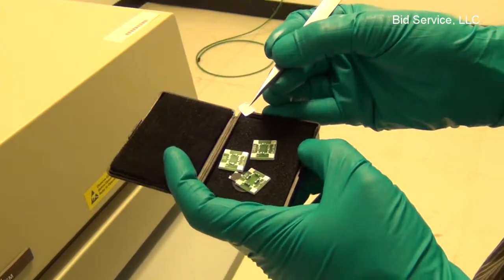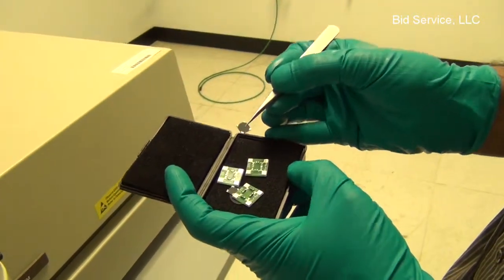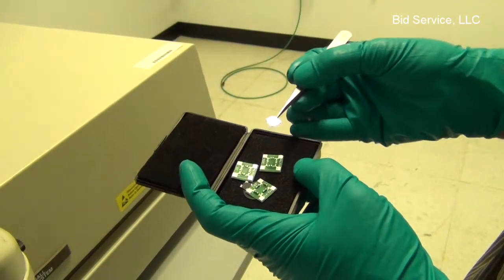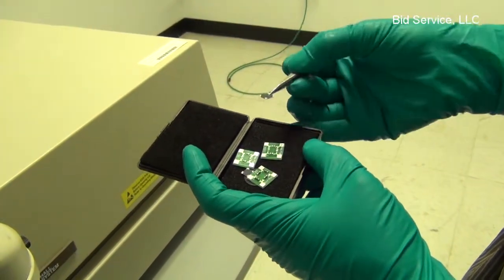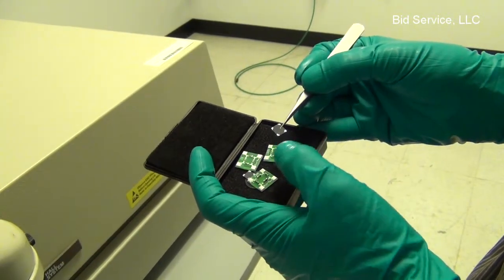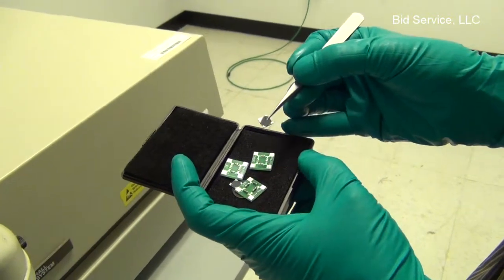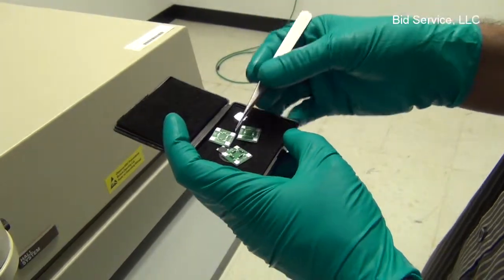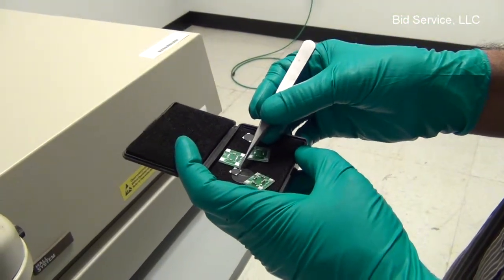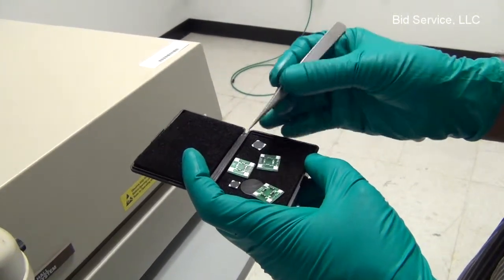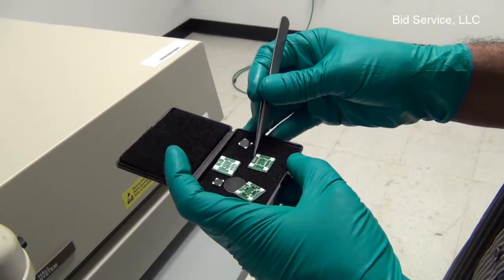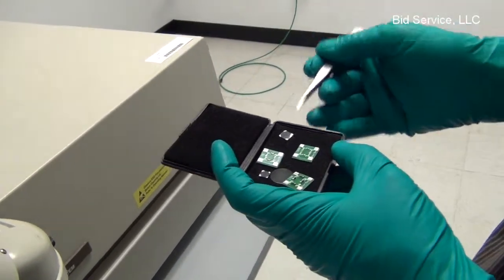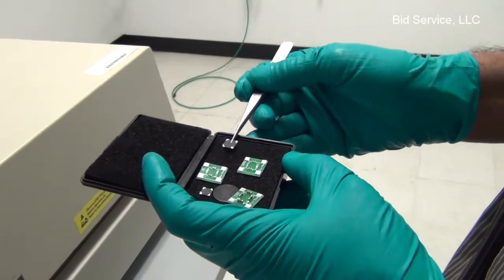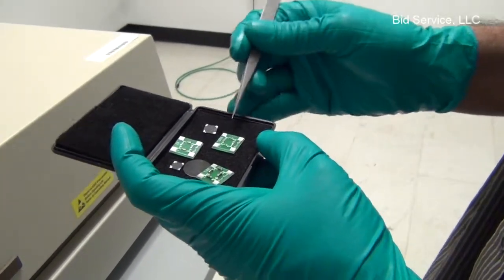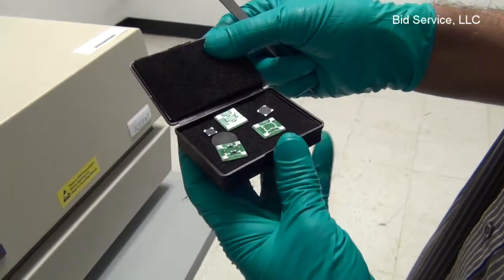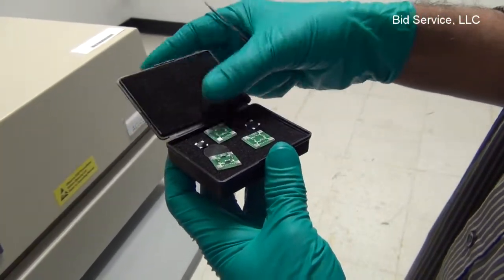The sample has to be properly prepared as per the manual procedure. The procedure is in detail. Here is a square piece of substrate with four contact points at the four corners. And rectangular samples also could be used, but there's a limitation on the ratio of the sample thickness to the length and the width. So the rules have to be followed as per the manual.